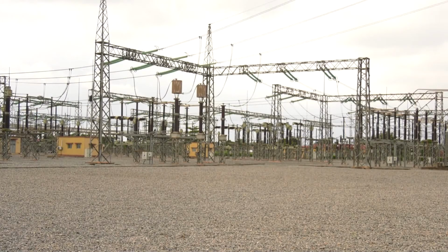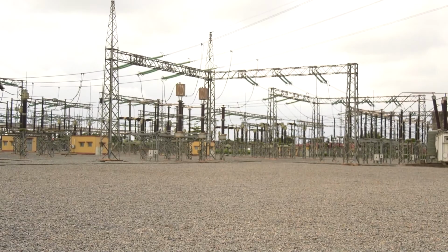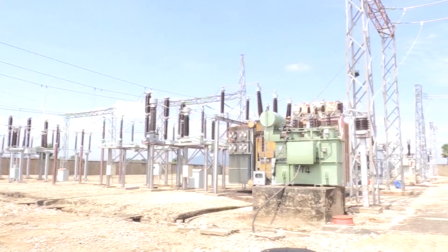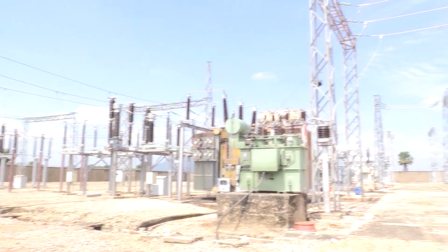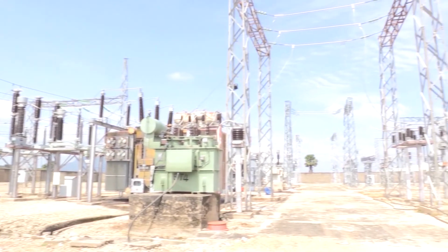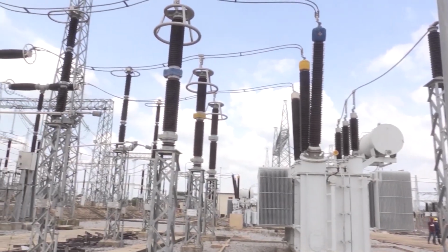We receive power from generation, not necessarily a particular one, because it's a grid. TCN as a whole is a grid. We receive power on the grid from our major substation, that is the 330 kV substation. From there we step it down to 132, and evacuate it to what we call the 132 kV, 33 kV substation.